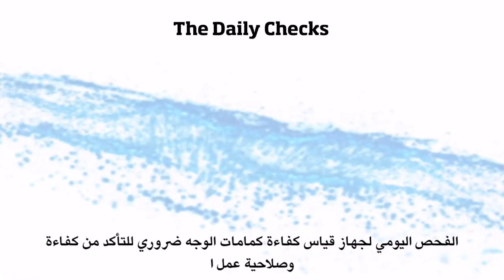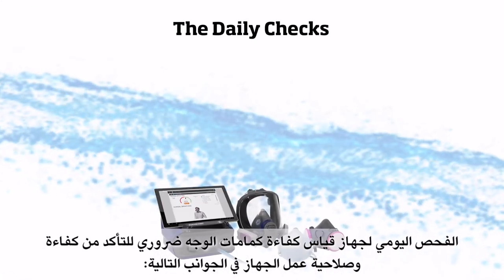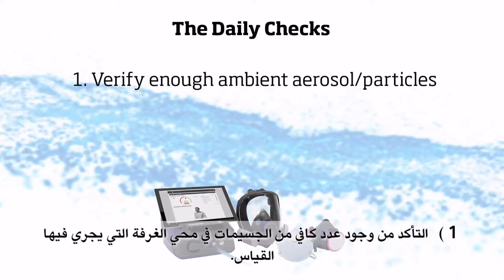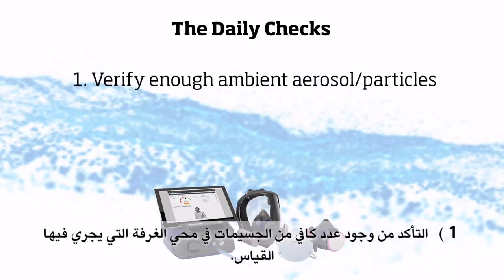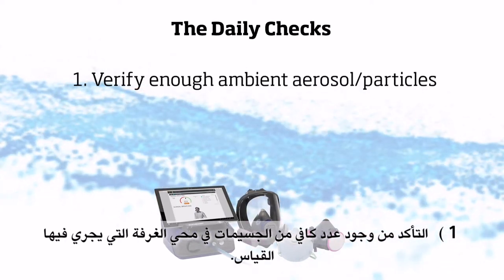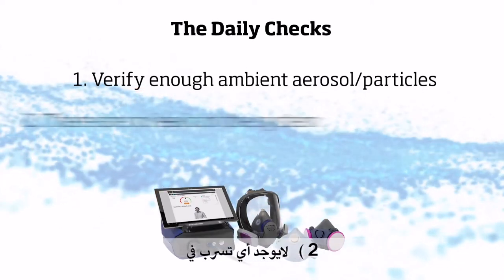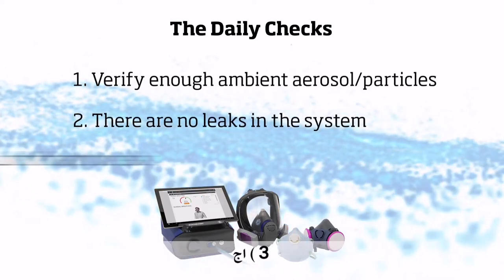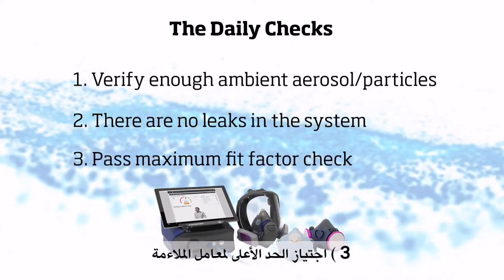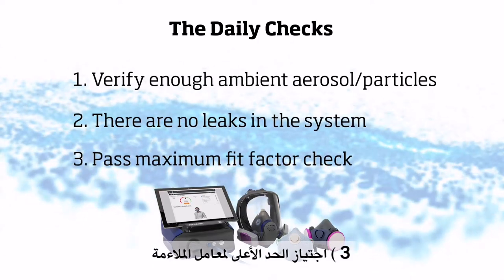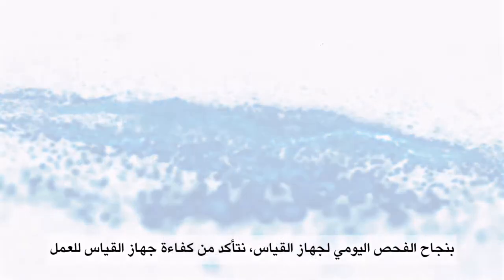The daily check does three things: it verifies there is enough ambient aerosol — a minimum particle count in the room — to conduct a fit test; there are no leaks in the system, a zero check; and it can pass the maximum fit factor check. Passing the daily check verifies the PortaCount is working properly.